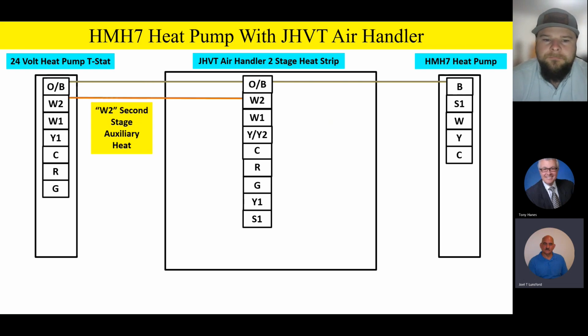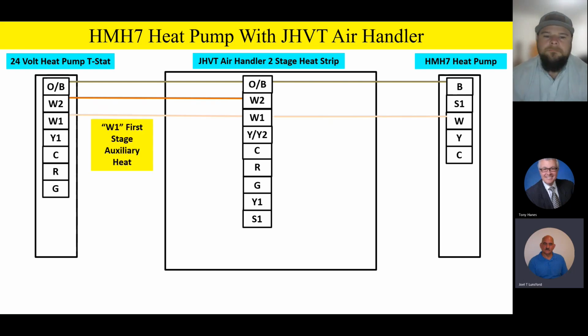W2 is our second stage auxiliary heat. W1 is our first stage auxiliary heat, and we're going to carry that all the way outside because remember, we want to bring on one stage of heat strip anytime we go into defrost. From that, we get a W signal from outside to bring the heat strip on during defrost so we don't freeze the homeowner out.